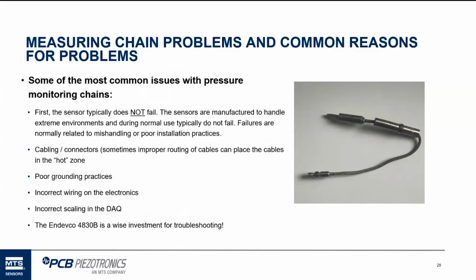You can see that sensor now. It was damaged because it got hit by something. It was installed inside the combustor too far, so it got hit by something within the combustor. Like I said, the sensors don't fail unless they're abused, mishandled, you know, installed improperly. They don't just fail when they're in normal use.